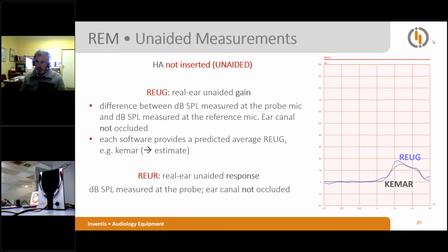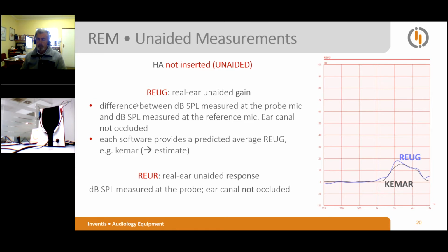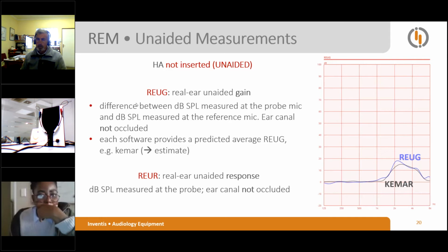Okay, so the kemar curve is the standard population curve, which always appears on the screen. The violet one is the curve acquired for the patient under test, the patient who is not wearing the hearing aid. Okay? That violet curve represents the value of the sounds acquired at the eardrum by the probe microphone. Okay? It is important sometimes to compare the kemar curve, which is the standard one, with the violet curve acquired in order to be sure that the user has inserted the silicone tube properly into the ear canal. Okay, hope so.